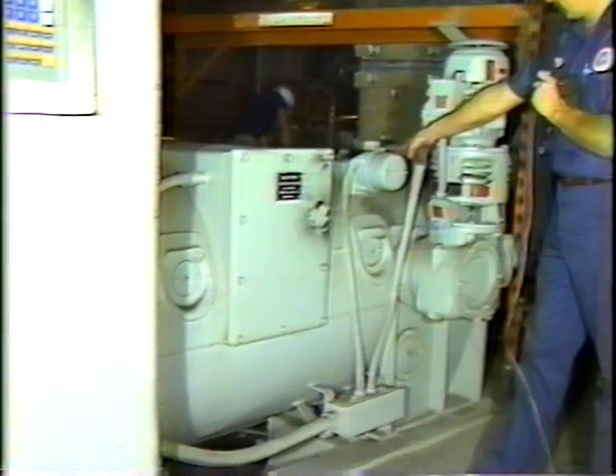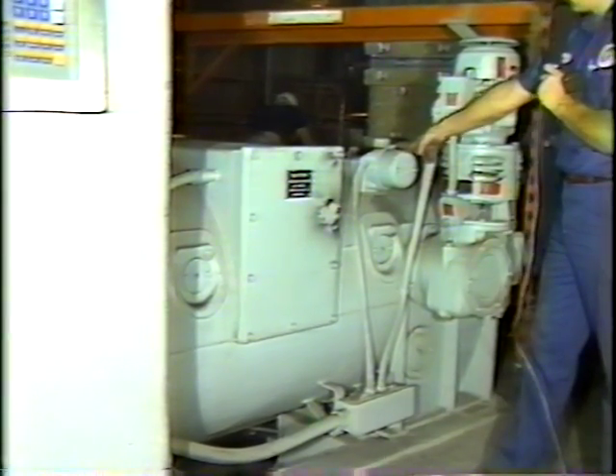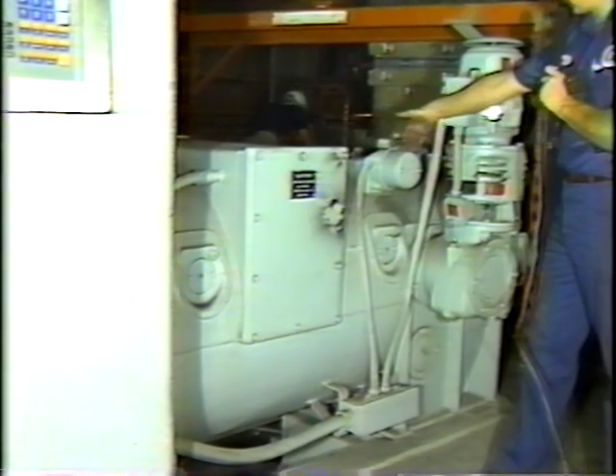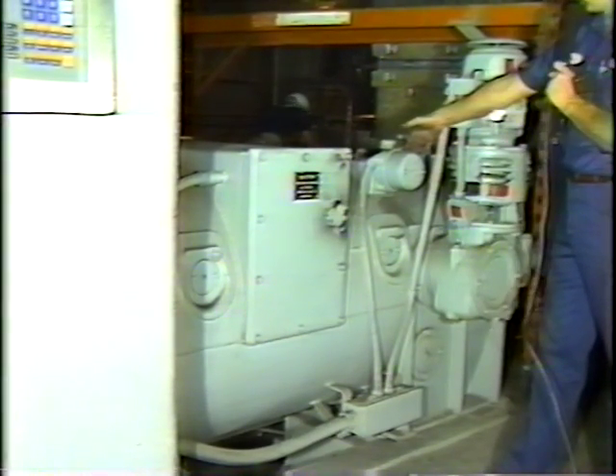There's a coal on belt indicator inside the feeder, which resembles a flag. The coal has to be present on the belt to make this switch up, which will allow the feeder and the rest of the equipment to operate. What we are now looking at is a window at the end of the stock gravimetric feeder, and through it we can see the coal containing upwards to 8% moisture as it discharges directly down into the Williams pulverizer.